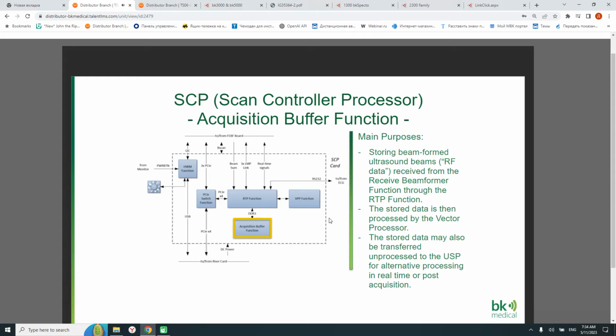The acquisition buffer function is storing beamformed ultrasound beams, also called RF data, received from the receive beamformer function through the RTP function. The stored data is then processed by the vector processor. The stored data may also be transferred unprocessed to the USP for alternative processing in real time or post-acquisition.